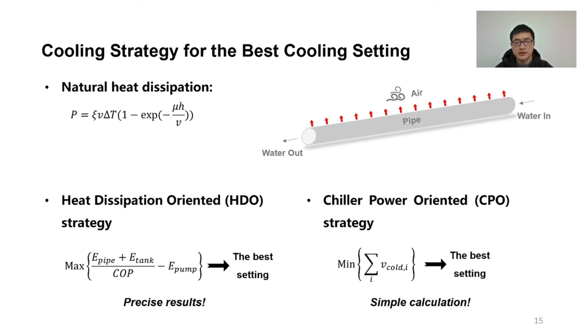Accordingly, we design a heat dissipation-oriented strategy. It calculates the amount of dissipated heat, converts the value to the energy that would be consumed by the chiller by multiplying the coefficient of performance of the chiller, and subtracts the energy consumed by pumps that is approximately proportional to the total water flow rate. By maximizing the final results, it can obtain the best cooling setting.